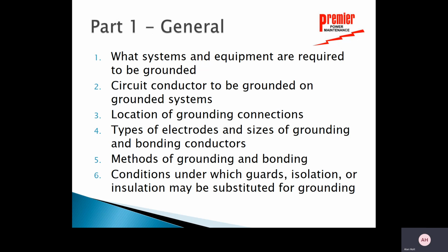So part one, general. When we talk about the general section of Article 250, it talks about what systems and what equipment are required to be grounded. You see, everything is not required, but it's very specific on those items that are required. Then we talk about the circuit conductor to be grounded on grounded systems. So for instance, a neutral on our house, that's a circuit conductor. That carries current, but it's to be grounded at certain locations. We'll talk about that. We talk about the location of grounding connections, where they are. It talks about the types of electrodes and the sizes of grounding and bonding conductors.